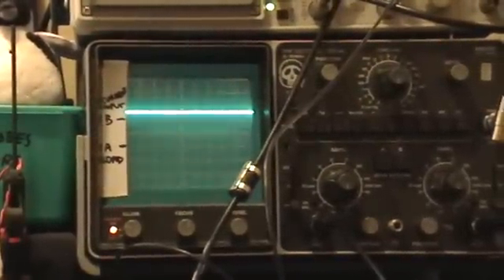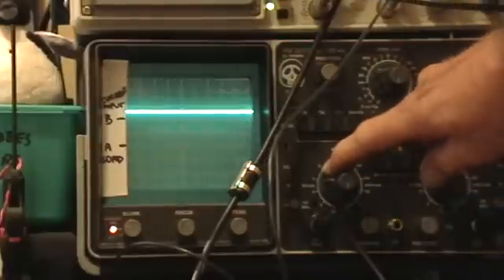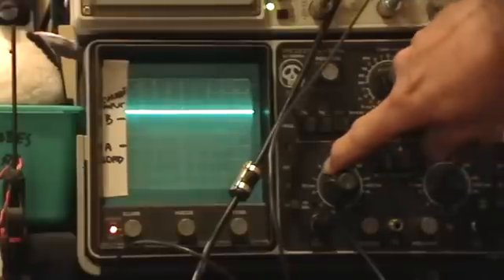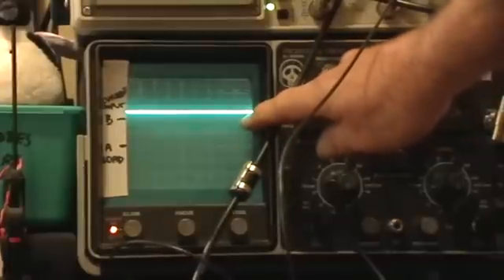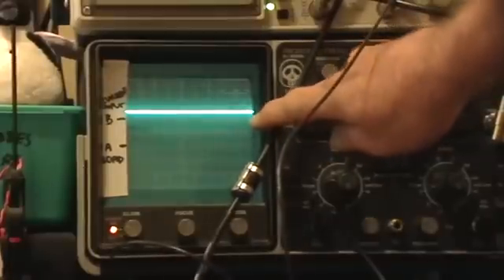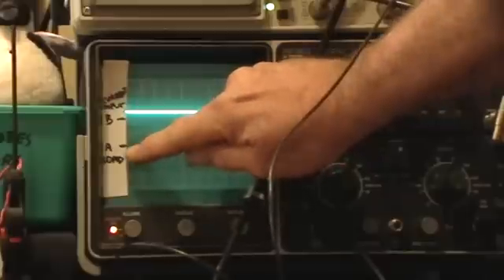I'm using a 10x attenuating probe. That means that the number you read on the voltage scale needs to be multiplied by 10. So we're on the 1 volt per division scale. You multiply that by 10.